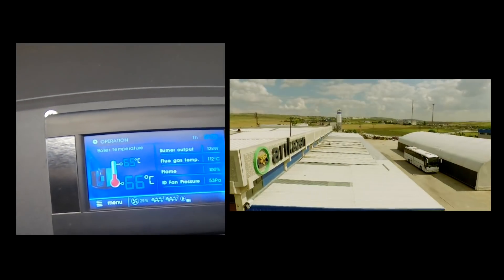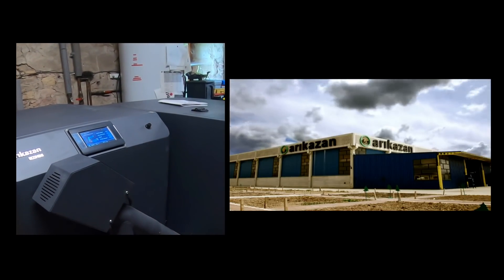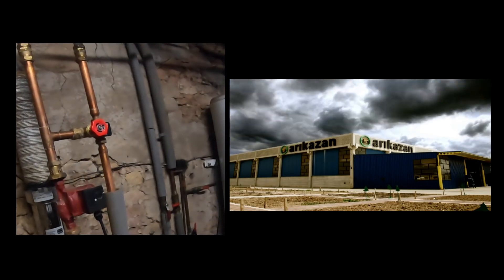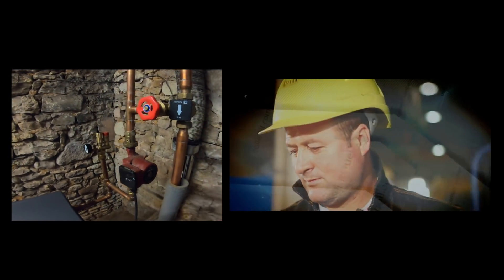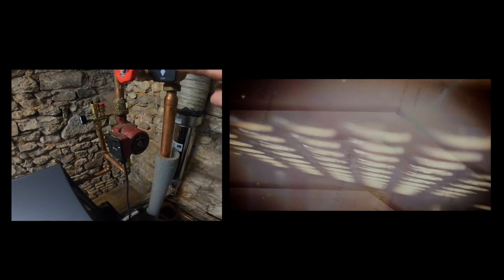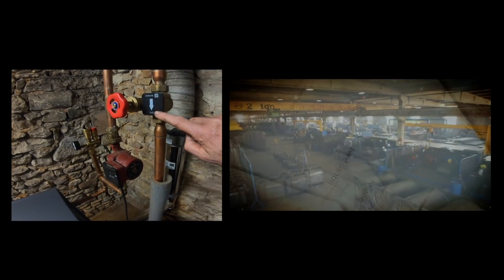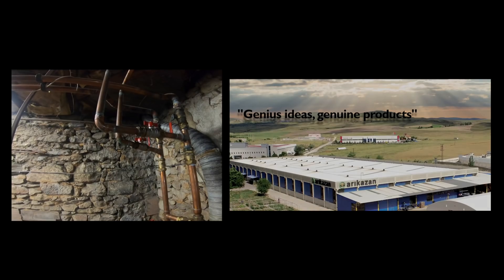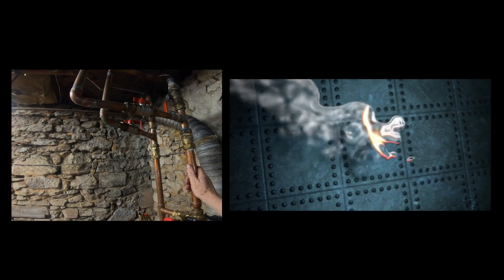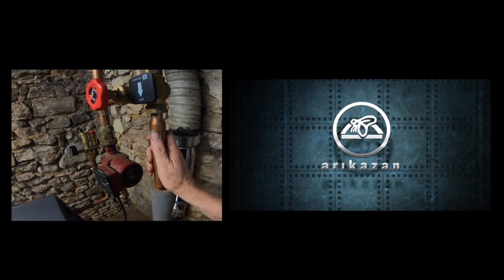There are tons of really cool bits of modern technology to make this beast work. One of my favorite parts is this box with the down arrow - the furnace heats itself up and then just cycles the hot water back down into the furnace until it reaches an optimum operating temperature of 55 Celsius. Then it flips and lets the hot water up into our old water mill heating system, so it's already preheated.